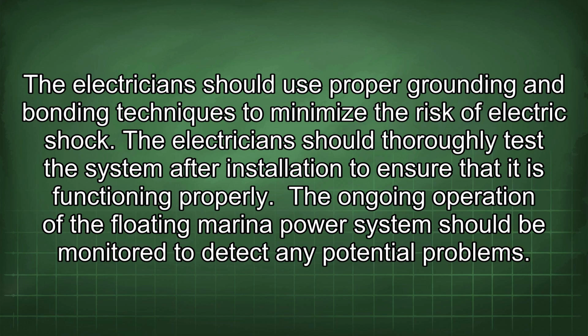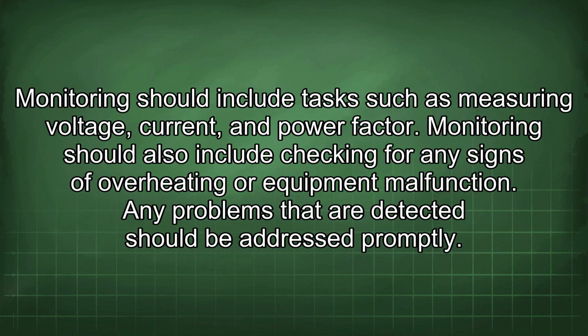The ongoing operation of the floating marina power system should be monitored to detect any potential problems. Monitoring should include tasks such as measuring voltage, current, and power factor. Monitoring should also include checking for any signs of overheating or equipment malfunction. Any problems that are detected should be addressed promptly.